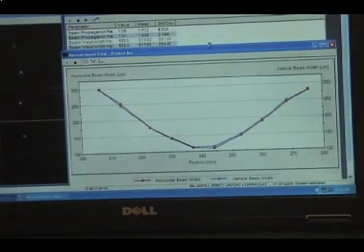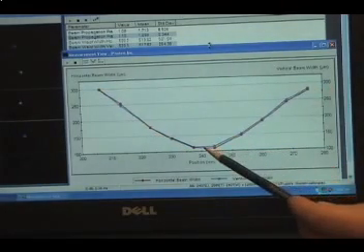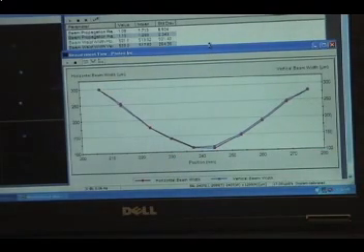Once we get all the beams lined up so there is one per cell, let's look at the beam waist caustic. Notice that there's about a three to one ratio between the beam at the waist and at the ends of the waist caustic. We want to use this ratio because it allows us to use the full dynamic range of this 12-bit CCD camera used in the 1780 mode scan system to measure the largest portion of the beam waist possible. If the ratio is much smaller than this, we are only measuring a very small portion of the beam waist. If the ratio is larger than this, the largest beams are measured using a very small percentage of the dynamic range of the camera which can lead to inaccurate results.